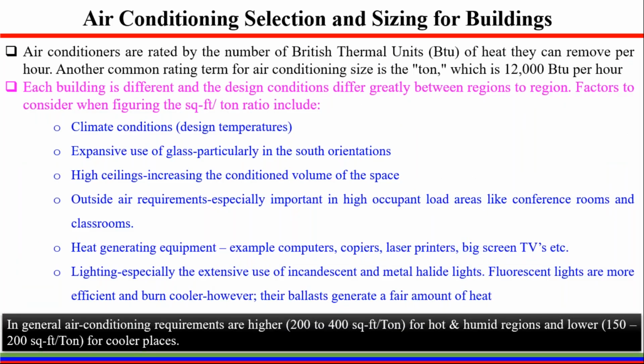The next two slides will show you the sizing of air conditioning for buildings. Air conditioners are rated in British thermal units, BTUs. Normally when you purchase your AC, it is 12,000 BTUs or 18,000 BTUs, and 12,000 BTUs is equal to 1 ton. So if you want to buy a 1 ton air conditioner unit, it is equal to 12,000 BTUs per hour.